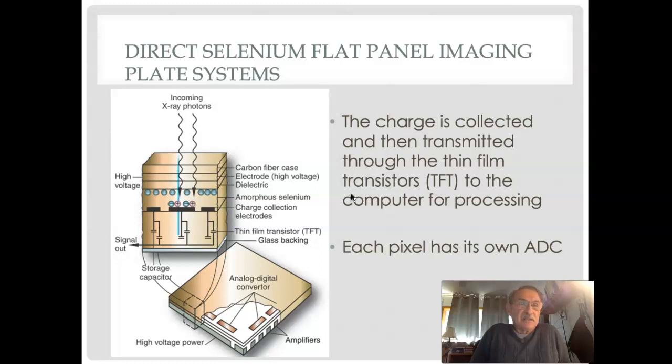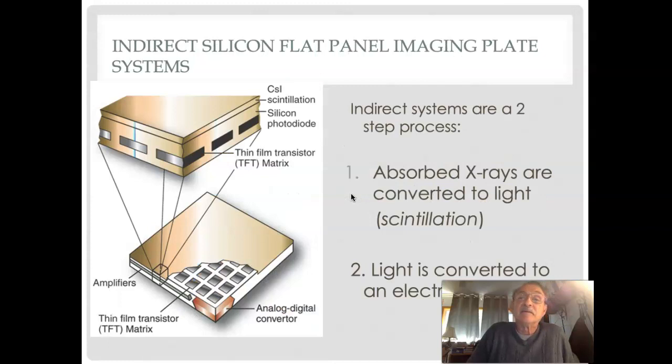For those of you who have studied electronics, you know that a capacitor is something that can store a charge, but then the thin film transistor, that is the gateway by which we upload the signal in its turn as a part of the signal to the computer. So that is, in a nutshell, the direct DR amorphous selenium paradigm of direct digital radiography.